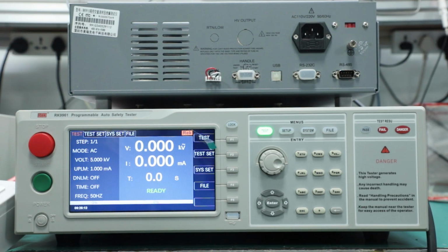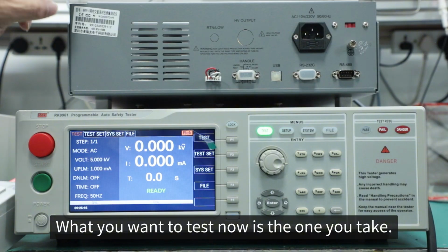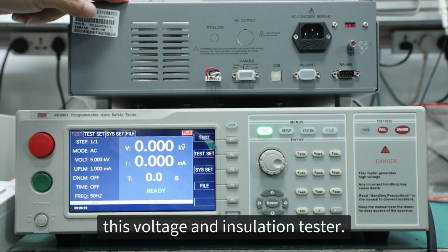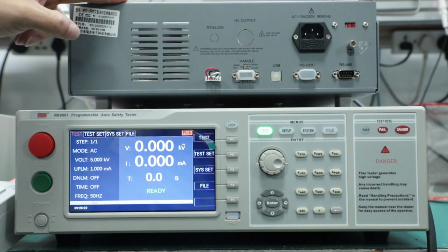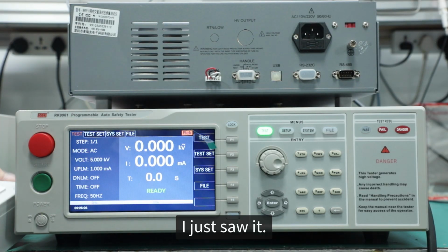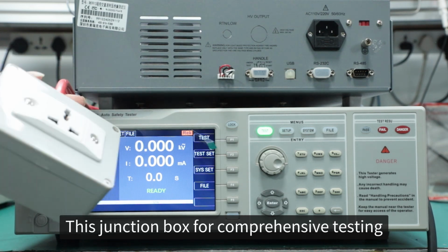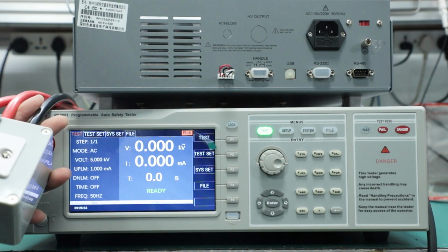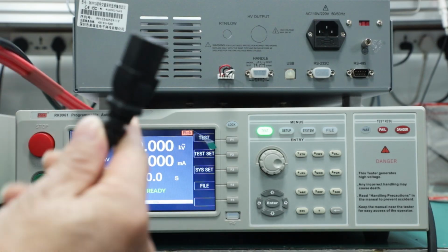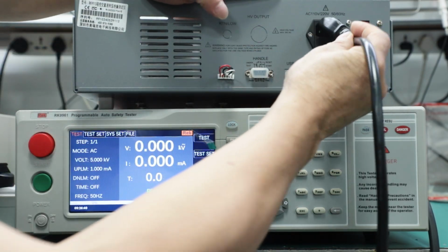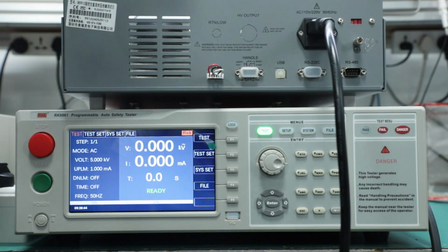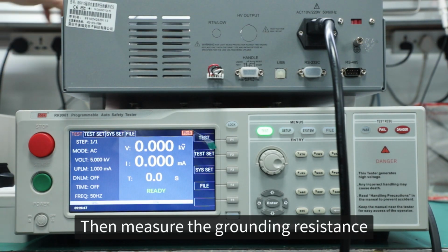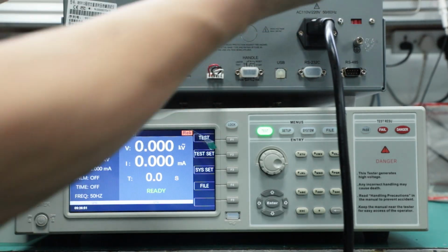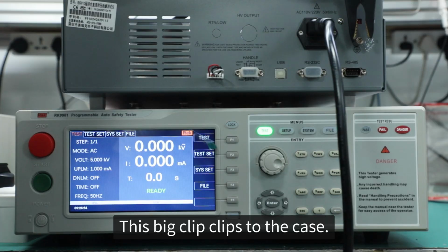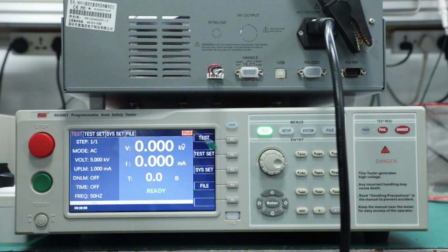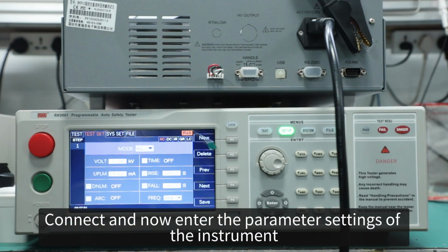Now, to test. What you want to test now is the one you take, the company's RK9961 voltage and insulation tester, as the test item. So let's start with this. This junction box for comprehensive testing is already connected. Plug in the power cord of the tested product. Then measure the grounding resistance: this big clip clips to the case on the metal conductor. Connect, and now enter the parameter settings of the instrument.